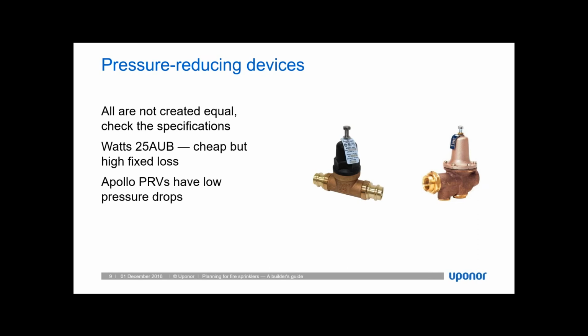Now, all pressure reducing valves are not created equal, and it is very important to find and note the pressure loss at the flows that you will see for that residential sprinkler system. 3/4 inch Watts 25 AUB is a very commonly used pressure reducing valve. However, it has a significant pressure drop, much, much higher than similarly sized Apollo pressure reducing valves.